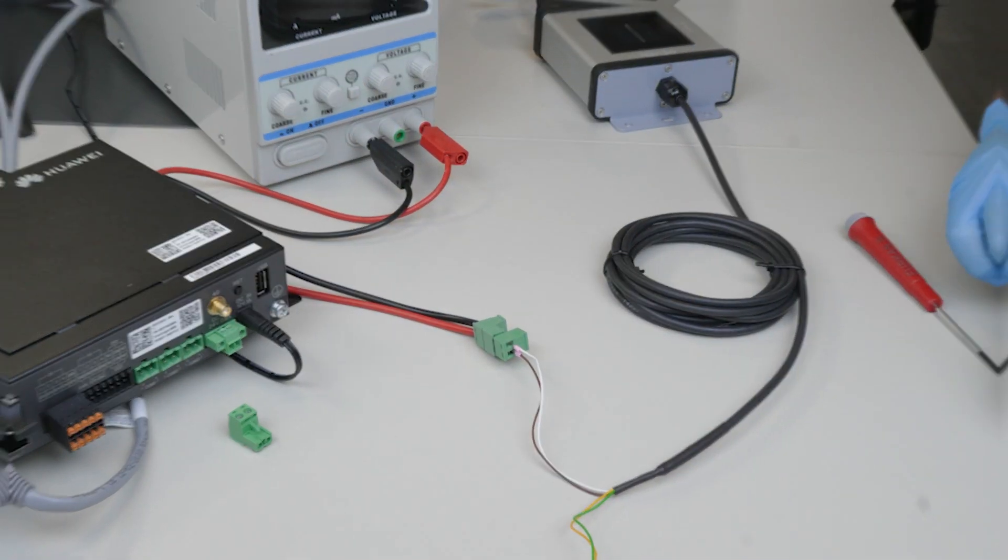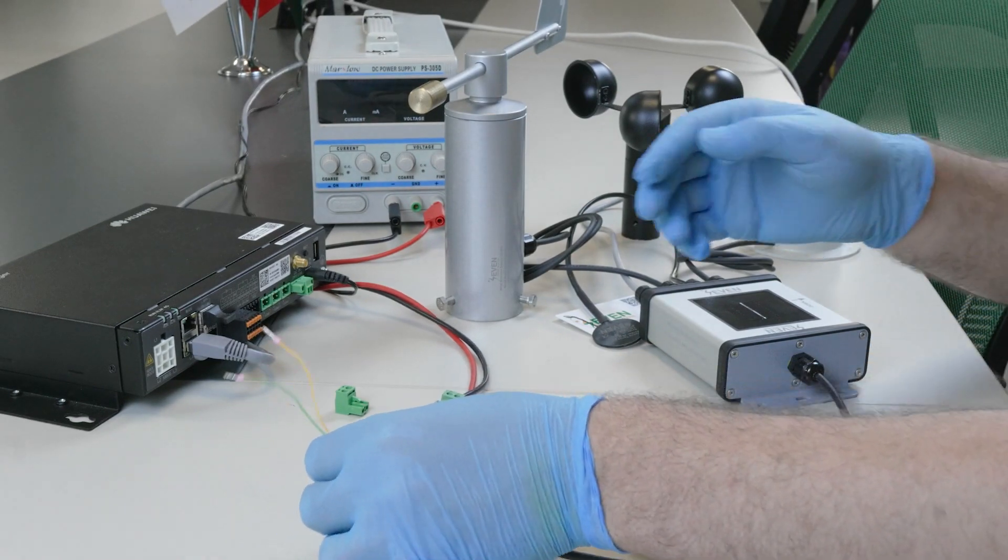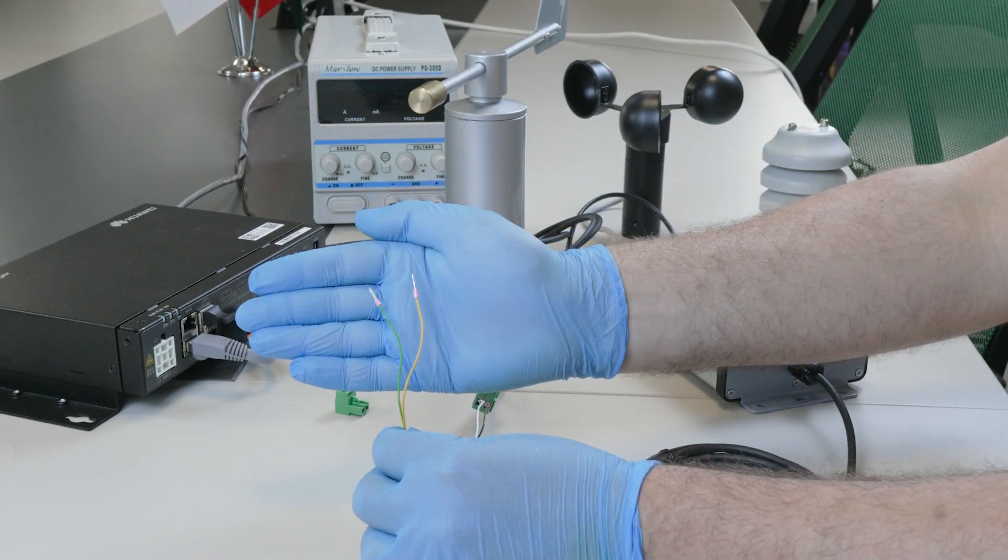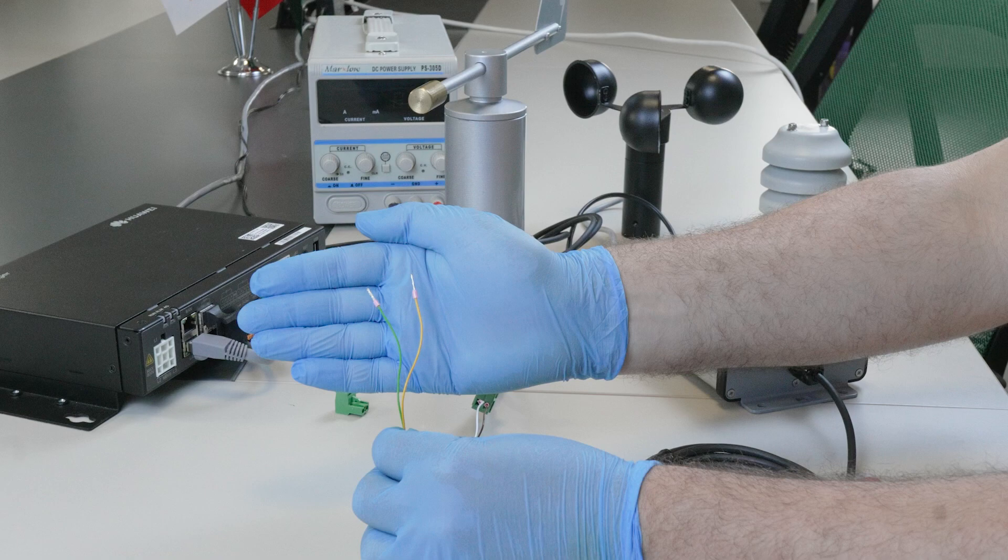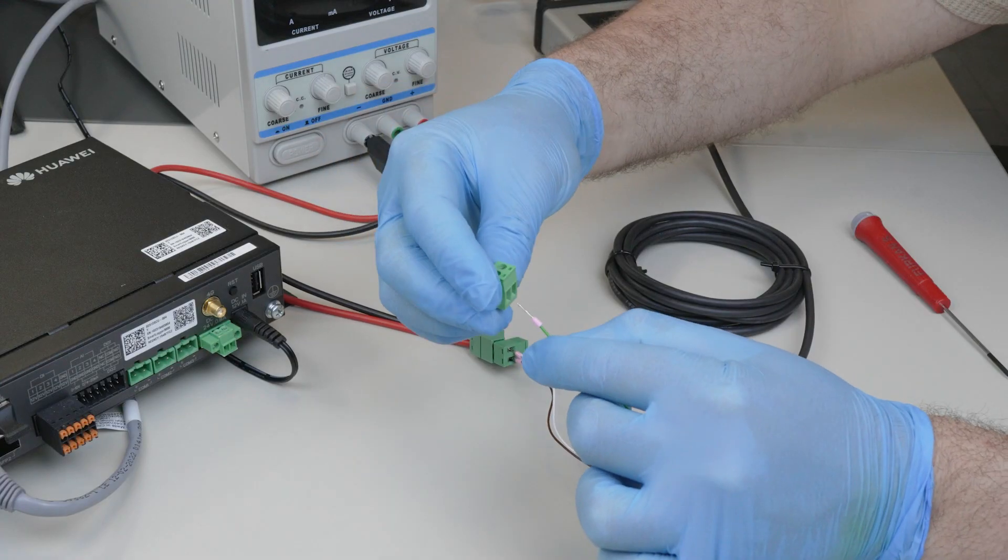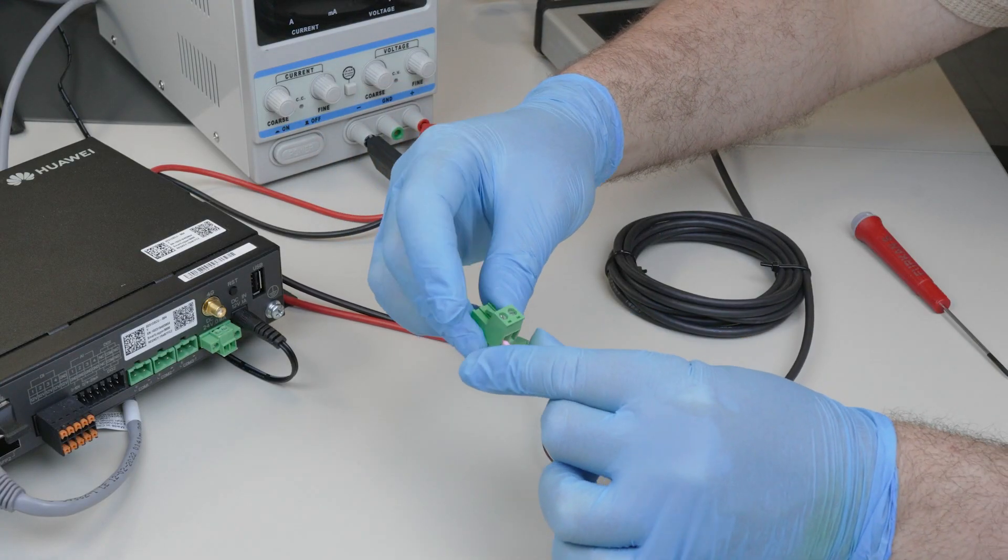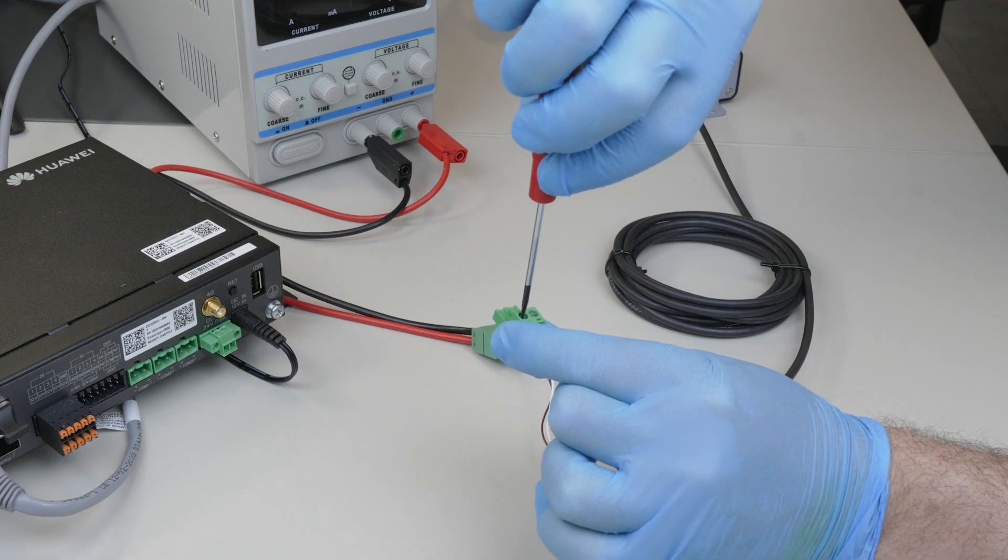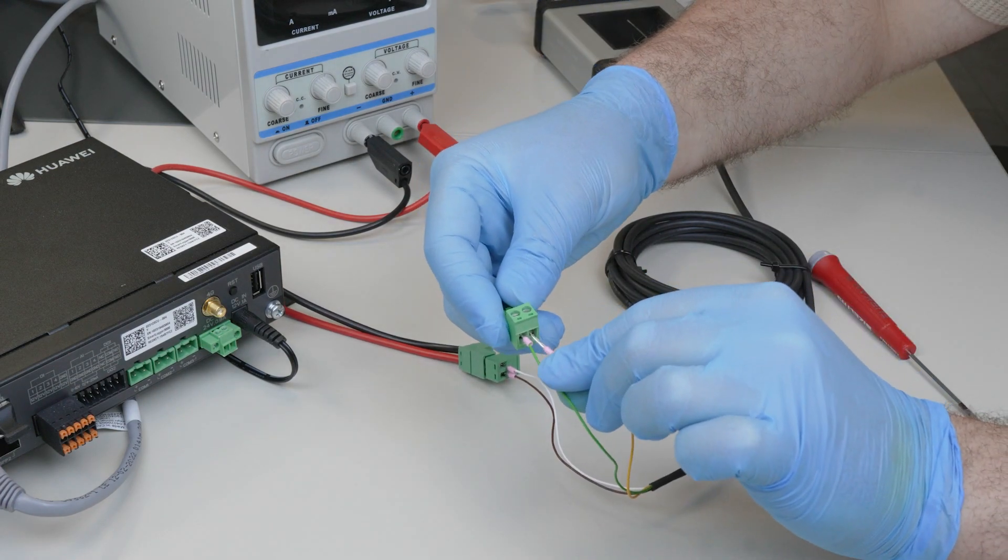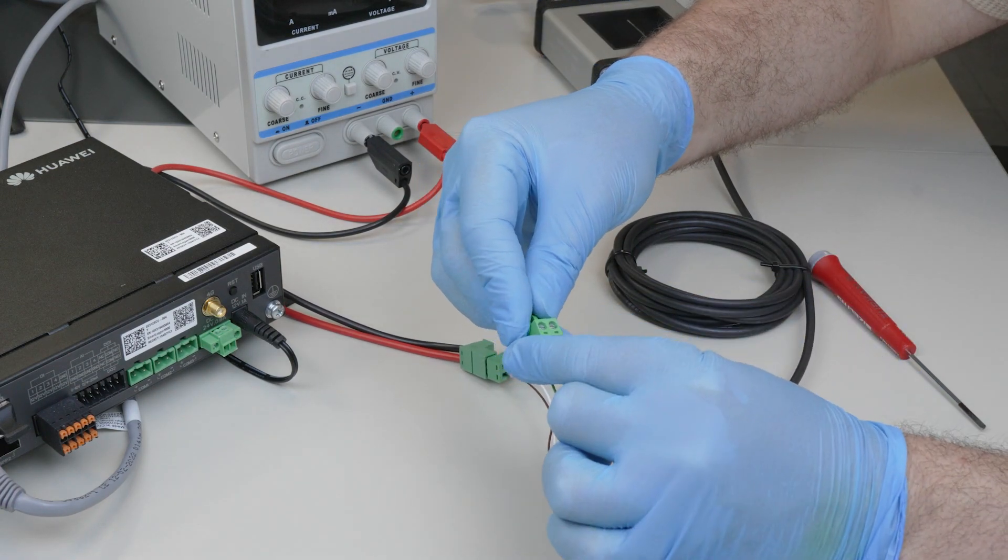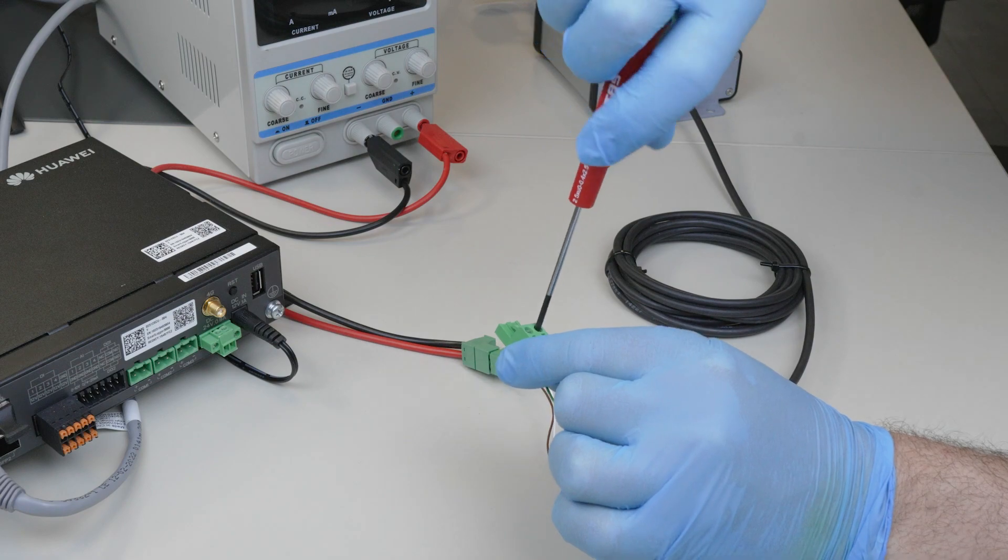The green and yellow wires are connected to the Modbus ports on the smart logger. The smart logger has three Modbus communication ports. After choosing which port you are going to connect to, connect the green wire to the input specified as data plus and the yellow wire to the input specified as data minus.